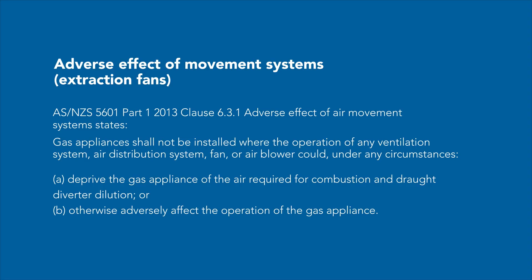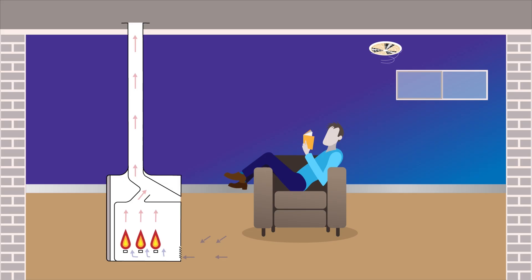Refer AS NZS 5601 Part 1 2013 Clause 6.3.1. Adverse effect of air movement systems states gas appliances shall not be installed where the operation of any ventilation system, air distribution system, fan or air blower could under any circumstances deprive the gas appliance of the air required for combustion and draft diverter dilution or otherwise adversely affect the operation of the gas appliance.